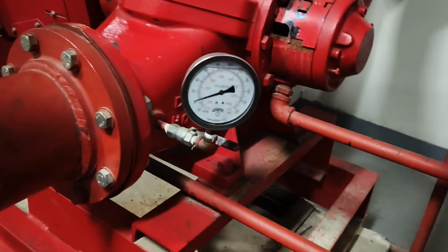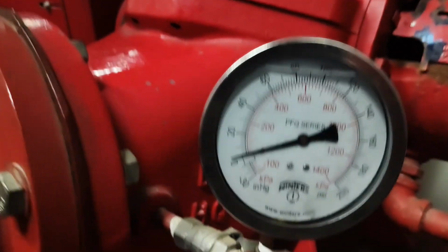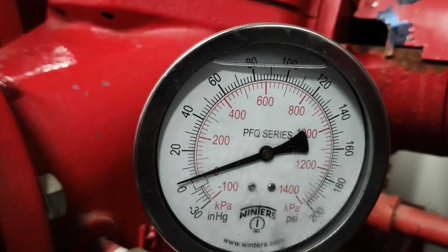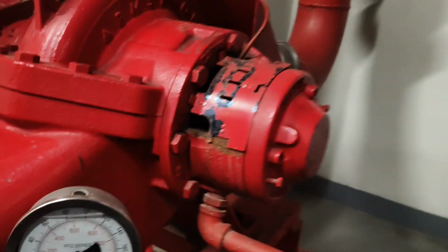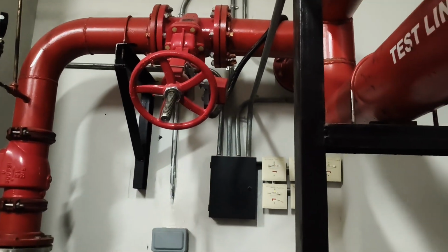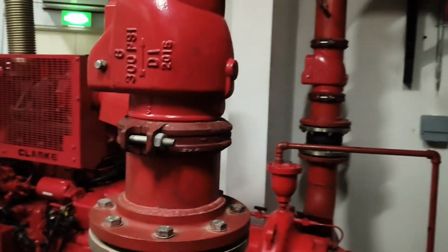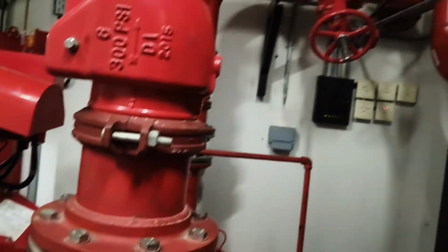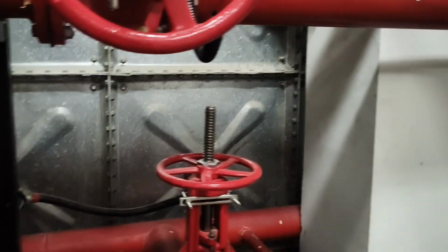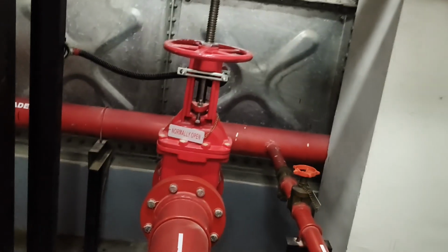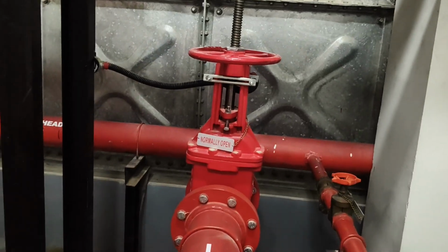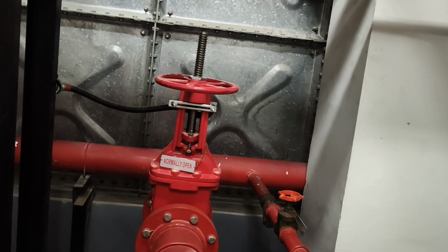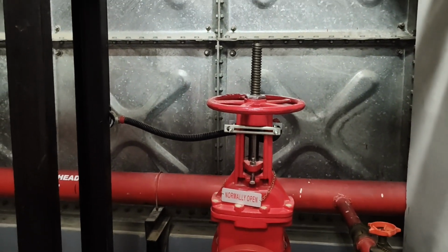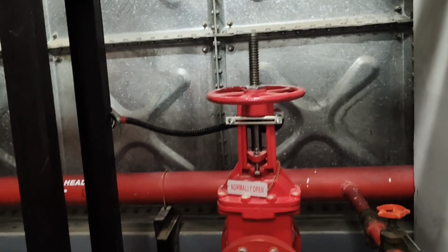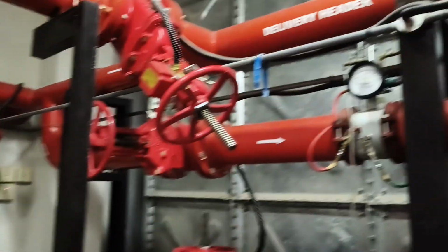The same thing, the diesel also has a suction pressure gauge. So this is the suction pressure gauge actually. It has a minus pressure gauge here, and the discharge pressure gauge is also there. And in labelings we make sure that these valves will be labeled in accordance with the systems that we have. So for example, if I tamper with this gate valve, it has to give an indication like electric suction gate valve. Then it will give that signal as supervisory or trouble that somebody has tampered with it. The same thing, diesel suction, and we have the discharge.